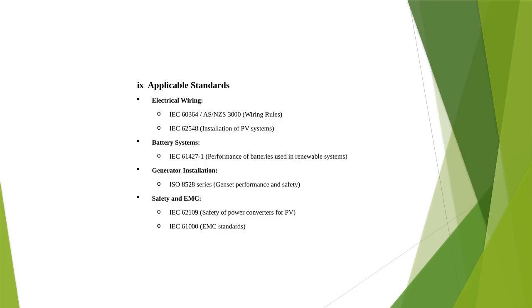For generator installation, that is the genset installation and its safety, it is going to conform to the ISO 8528 series. Then for safety and EMC standards, our system will conform to IEC 62109, safety of power converters for solar panels, and also IEC 61000 EMC standards.